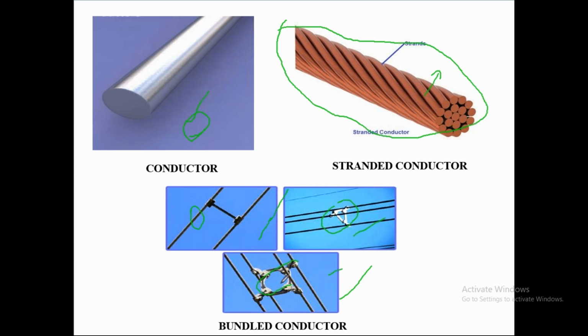Bundle conductors are preferable where the voltage level is greater than 230 kilovolts. Strand conductors can be used between 100 and 200 kilovolts, and the other type can be used for less than 80 kilovolts. So based on distance, capacity, and cost, we use different types of conductors in different areas for different applications. In this class, we are going to discuss bundle conductors and strand conductors — how we can use these types of conductors.